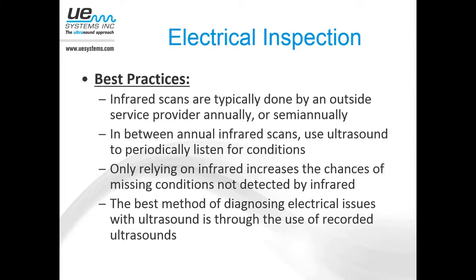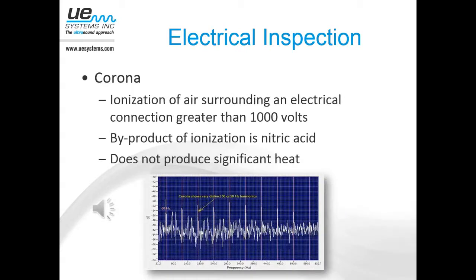Again, there are certain types of issues that you're going to pick up that you won't pick up with infrared, and vice versa. So some ionization issues, some intermittent tracking and arcing problems don't really produce a lot of heat, so it's something you really want to pay close attention to. Just a couple quick sound files here I'll play for you, just so you have an idea of what I'm talking about. Corona, which is essentially just ionization of the air.